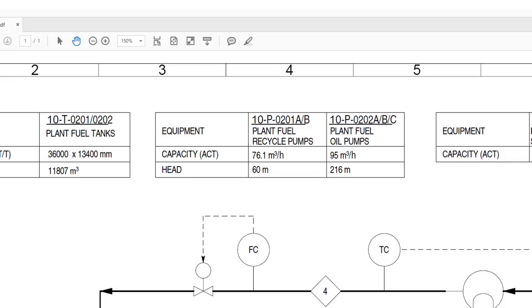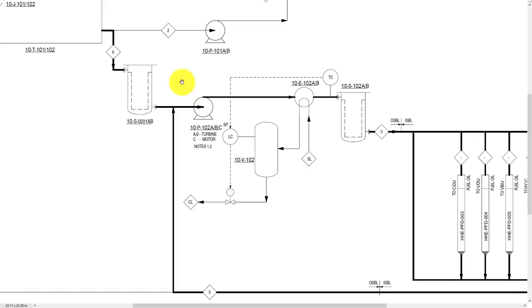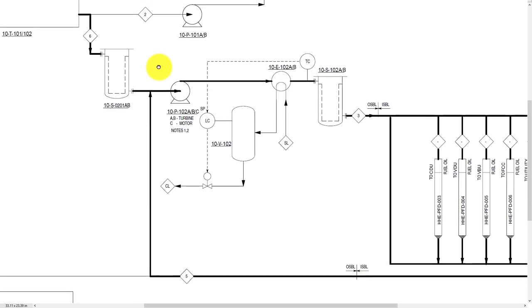See this detail of the pump. Recycle pump has a head of 60 meters and the plant fuel oil has a head of 216 meters. This must be a huge pump. Let's look where they are on the PFD.